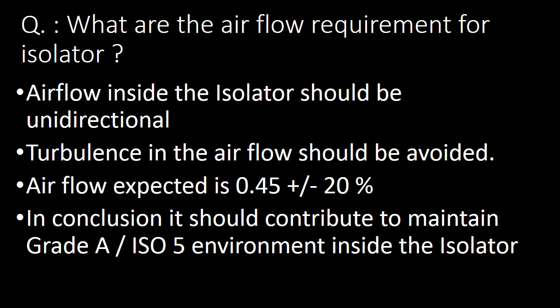Airflow expected is 0.45 m/s plus or minus 20%. In conclusion, it should contribute to maintaining a Grade A or ISO 5 environment inside the isolator.